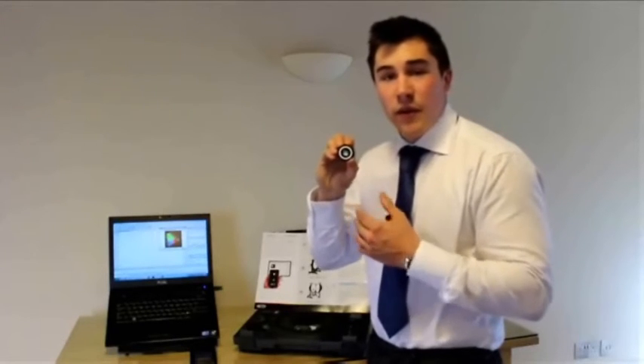This is basically used so the spectrometer can sense exactly which receptor head is being attached and appropriately apply the right software calibration file for that accessory. This saves the user time that would have to have been taken to go manually in the settings and change this.